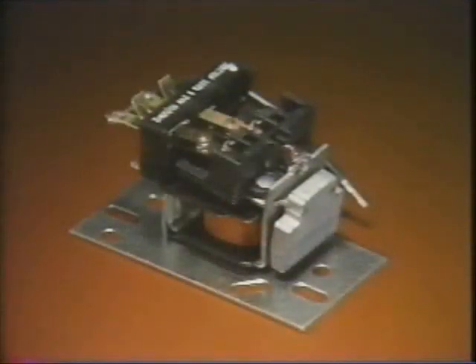Contact resistance is important when switching very low currents, such as in millivoltage circuits. Load-rated contacts have flat surfaces that can collect dust or silver oxides. Heavy loads, or line voltages, can blast through this, but light loads sometimes can't. So it's important to remember that relays used in millivoltage circuits should be rated for that service. Some Honeywell relays use gold flashed contacts for reliable millivoltage switching. A thin layer of gold on these contacts produces very low resistance and also guards against corrosion.